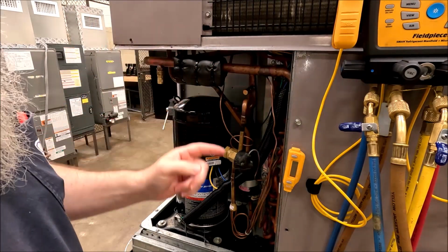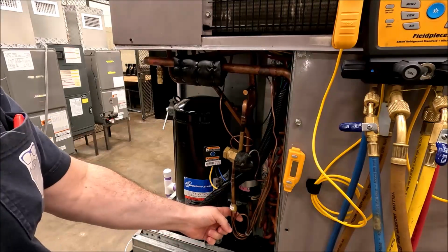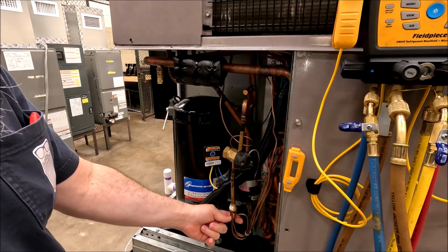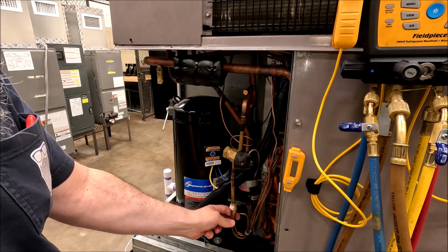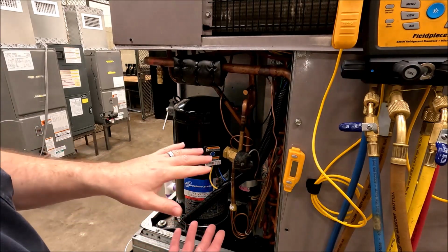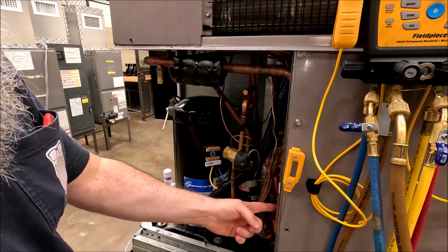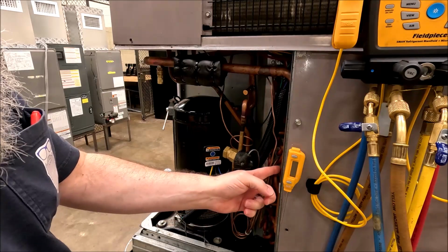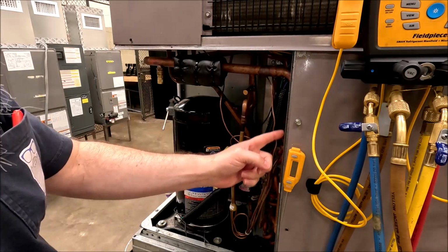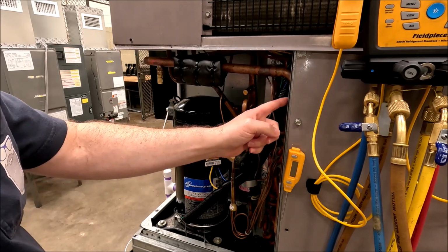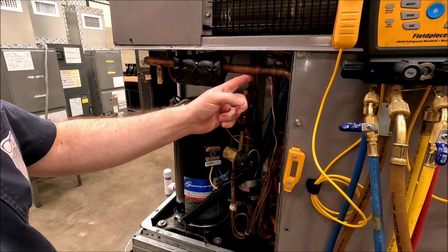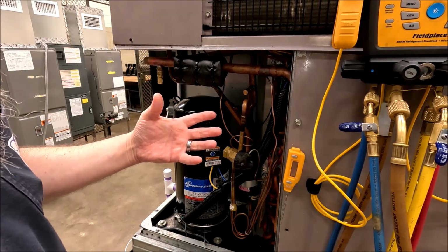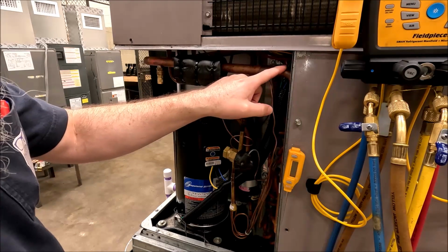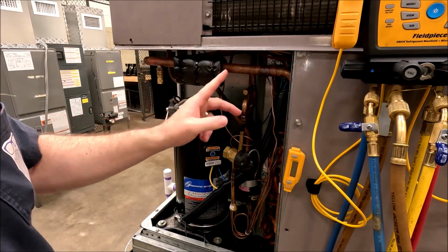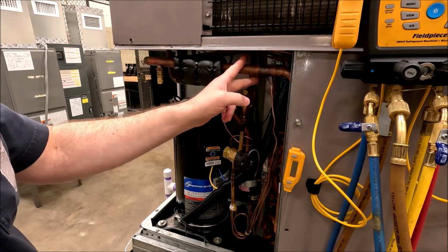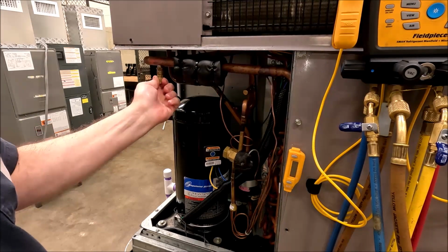If you don't trust it, look at where every time you get this distribution area coming out of the metering device, it splits 3 times and it goes into each section of the evaporator. They all come back, and right here, right on this panel area is a larger vapor line, because vapor takes up more space than the same amount of liquid. So that is my vapor line. I'm going to check superheat right here. My pressure tap is right there for my low side.